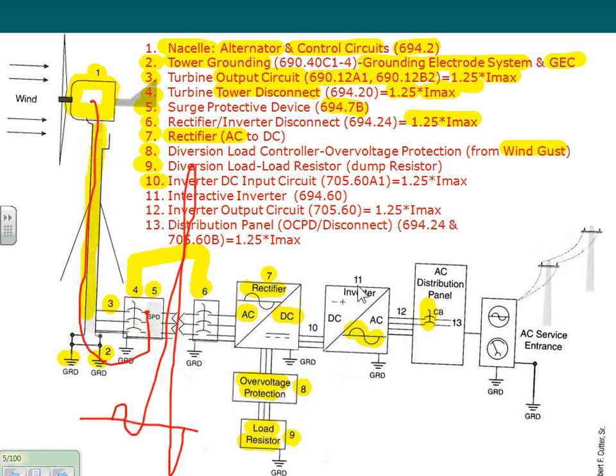Number 10, we're electricians, so what do we care about here? We care about wires. So the inverter DC input, we call this circuit inverter DC input, and guess what, that magic number keeps repeating itself. Now we took the AC, we rectified it to DC, and we're going to dump it into the inverter. Now you go to the inverter and you see what's the maximum current that the inverter is rated for. Say it was 100 amp, you multiply it by 1.25, you get 125 amp, and you size your conductor based on 125 amp.